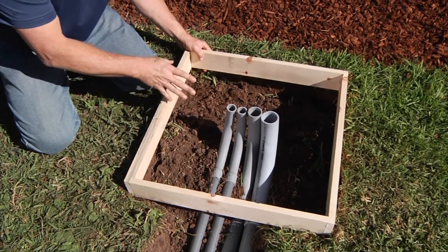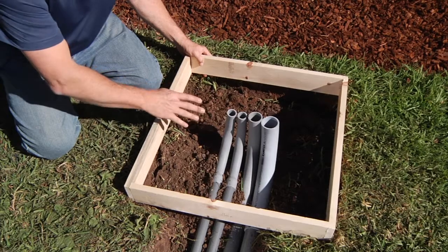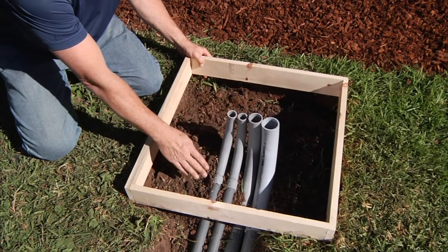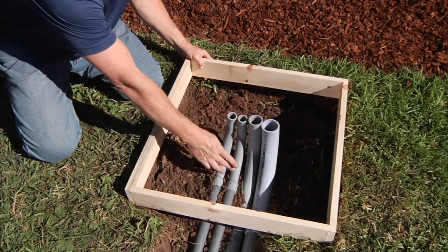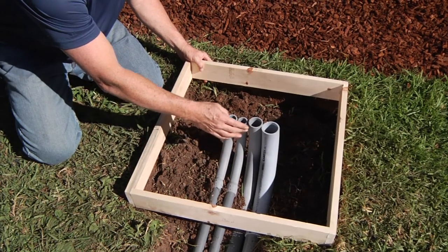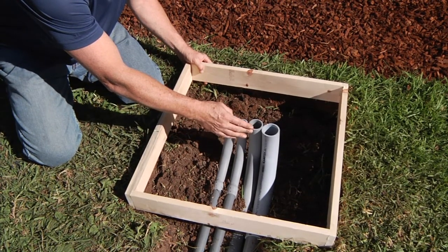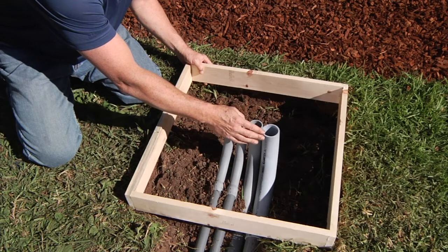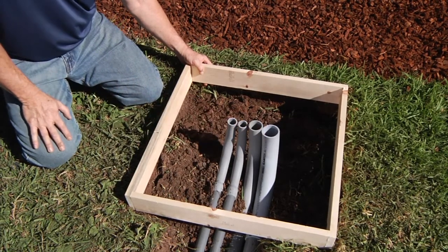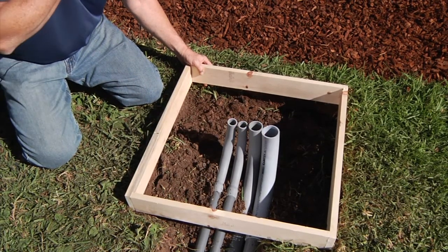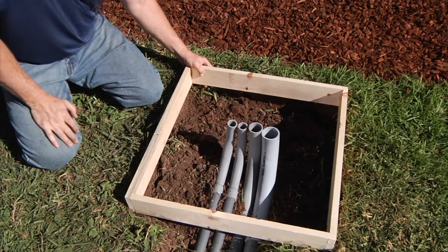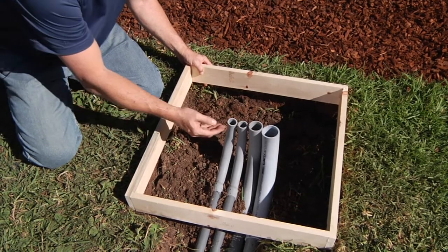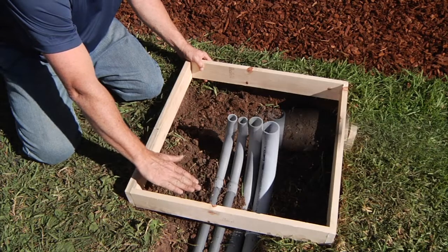We have the various conduits positioned here inside the form. We have 2 1-inch conduits, one for the incoming power supply and one for any future communications needs. The next conduit is 1 1/4 for grounding, and the final conduit in this case is 2-inch, and that will need to be sized depending on how many field wires you have going out to your valves. We'll want to make sure we have at least 3 inches of conduit above the cement base.